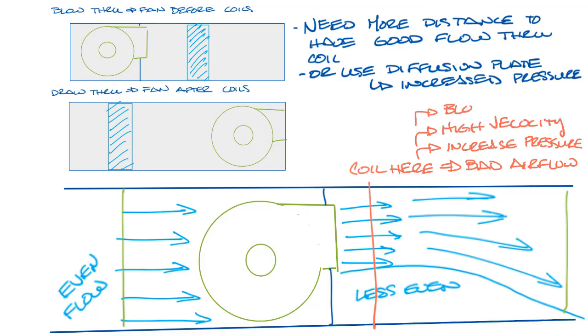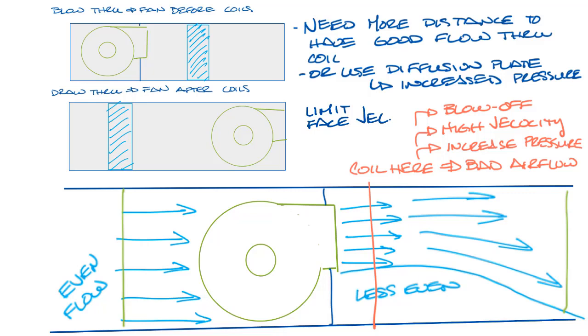And this high velocity could actually cause something called moisture or condensate blow-off or carry-over. This is when water droplets are blown off the coil and into the air stream, and you don't want water droplets in your air stream or in the ductwork, so you should limit your cooling coil face velocities to about 500 feet per minute, plus or minus 50 feet per minute, and have good air flow over the coils.